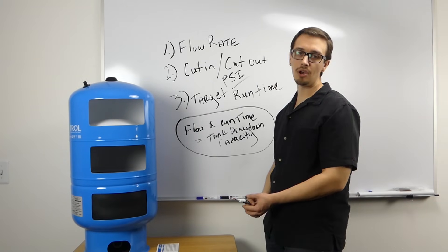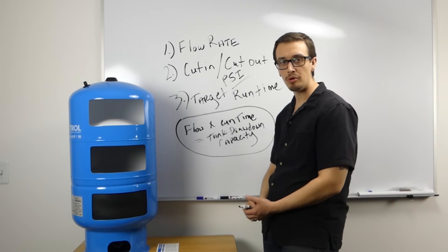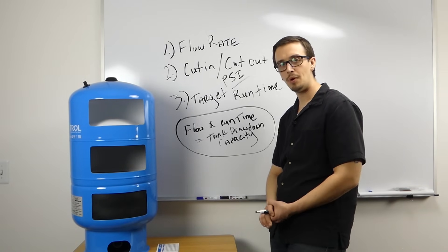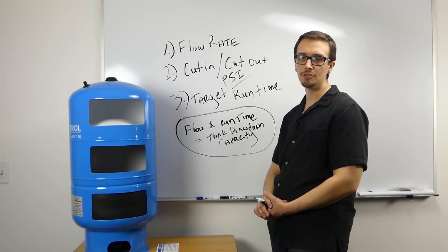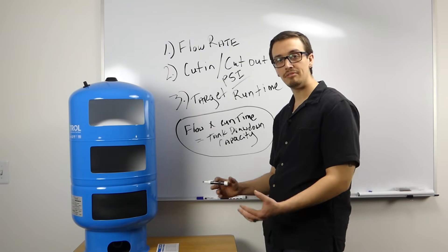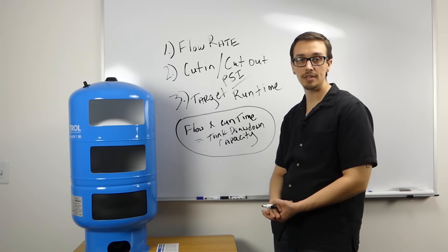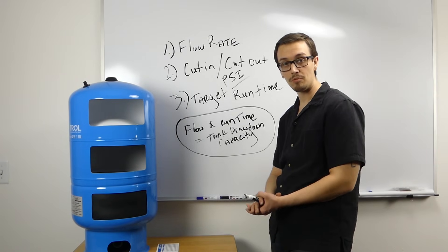Once your flow rate gets beyond about 10 gallons per minute up until about 20 gallons per minute, the target number increases to about one and a half gallons of drawdown per gallon per minute rating on the pump.